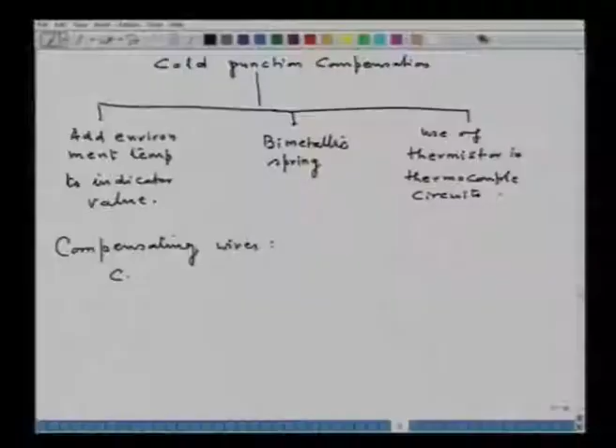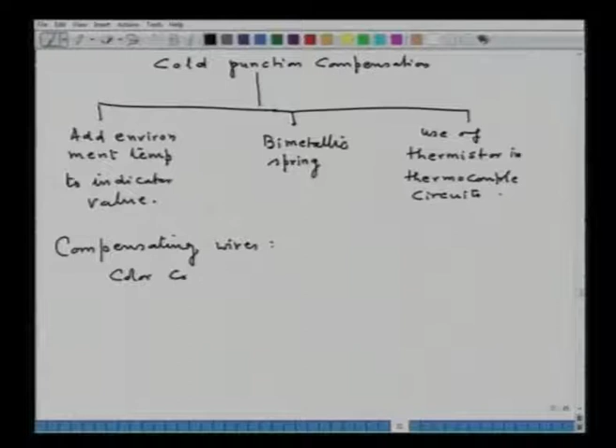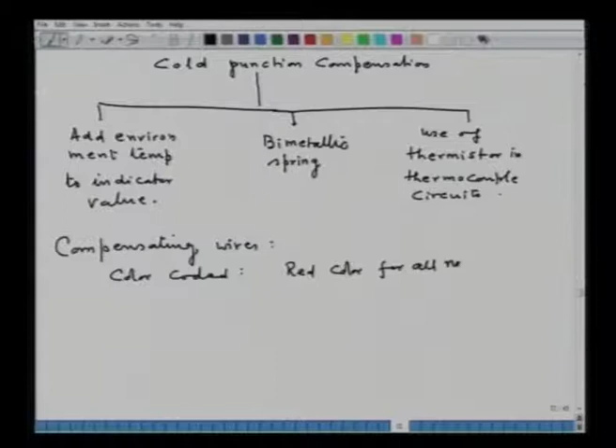So, normally they are color coded, say red color for all negative wires, whereas for the positive wire, say for a thermocouple J type it is white, for thermocouple K type it is yellow. In the previous table I listed J, K and all. For T type it is blue, for E type it is purple, and for N type it is orange. So, accordingly these wires should be used.